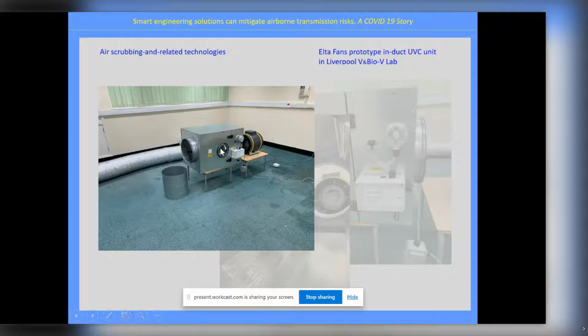There's a fan perched on a table, and it's going to blow through this unit, which is lined with high-power ultraviolet mercury tubes. This is the view from one end, looking into the chamber, again lined with aluminium, not stainless steel, aluminium, which is highly reflective of UVC light.